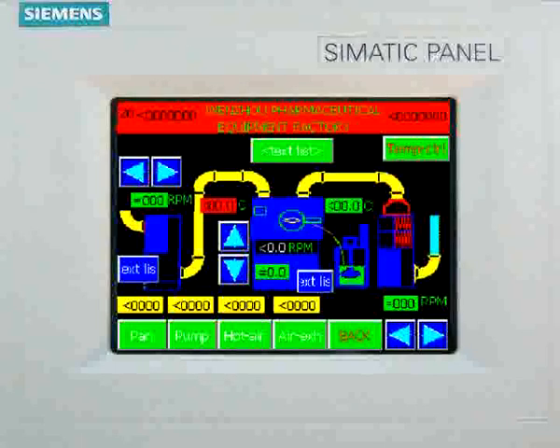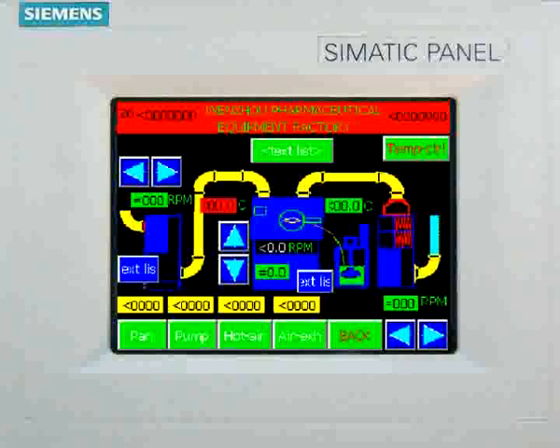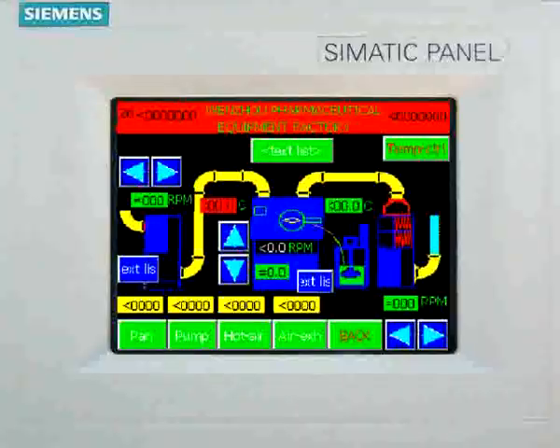5. Upon completion of the prior step, close the circulating water valve and open the discharge valve to discharge the water out of the rinse tank till the lowest water level. 6. Open the pure water supply valve. The pressure pump will start running. Open the corresponding discharge valve for the last circle of re-cleaning with pure water. Upon completion of timing running, stop the pressure pump and close the water supply valve. Close the drainage valve when the water in the rinse tank falls to the low water level.